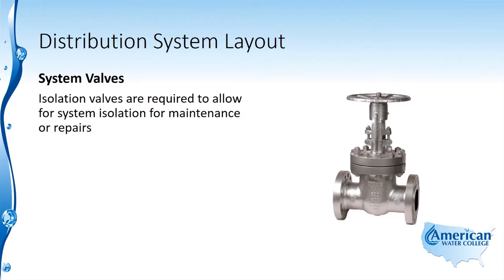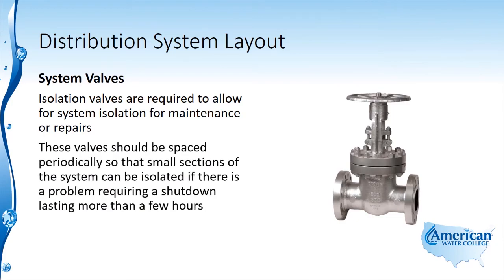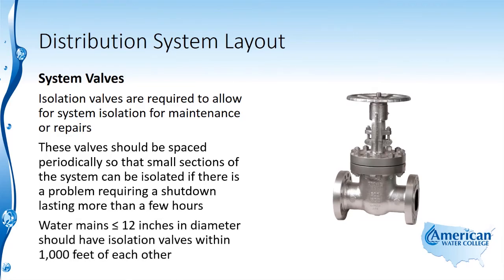Isolation valves are required to allow for system isolation for maintenance or repairs. These valves should be spaced periodically so that small sections of the system can be isolated if there is a problem requiring a shutdown lasting more than a few hours.